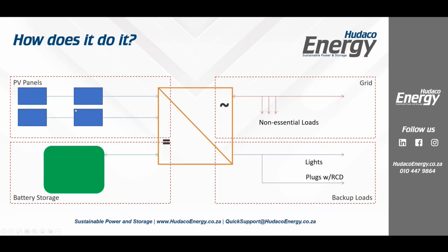So maybe we're producing 13 kilowatts of PV power. Let's use 10 kilowatts. Maybe we've got 10 kilowatts installed. We're producing 10 kilowatts just because it's an easy number to work with. At the same time, I can charge my batteries with up to 6 kVA. I can run 6 kVA loads here, and I could export up to 13 kVA there, all at the same time if I had enough power.